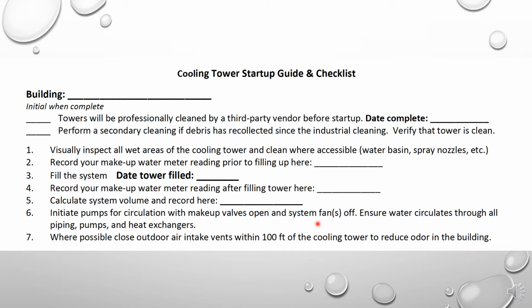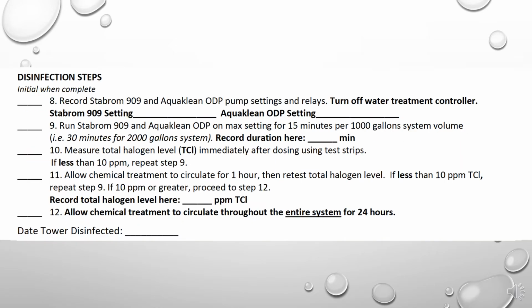You might want to consider alternating different pumps if you have to do that to make sure that you're able to circulate water through the entire system. And then where possible, close outdoor air intake vents within 100 feet of the cooling tower. You want to reduce any chemical odor that might be drawn into the building. So these are our disinfection steps, just like last year.